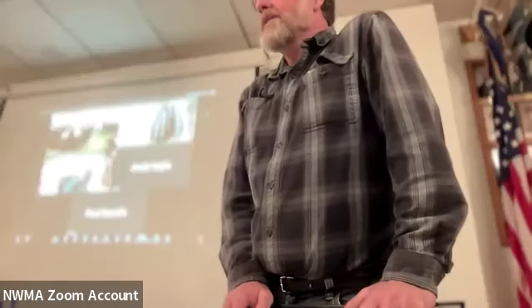My personal preference would be to have a circuit breaker that you can reset. There isn't a standard I'm aware of where you can get in trouble using a circuit breaker instead of a fuse. Typically, a breaker is more expensive, so you have more financial outlay immediately, but it's a more robust design in that you can reset it.